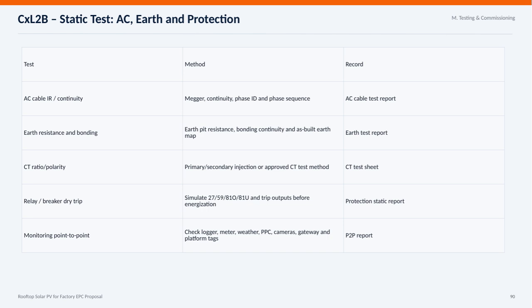Then we check the CT ratio and polarity through primary or secondary injection methods or other approved CT test procedures, recorded in the CT test sheet. For protection, we simulate various relay and breaker trips before energization, including functions like 27, 59, 81O, and 81U, ensuring protection systems operate correctly. These results go into the protection static report. Finally, we verify monitoring systems by checking loggers, meters, weather stations, PPC, cameras, gateways, and platform tags, with findings summarized in the point-to-point report. This comprehensive testing ensures all safety and performance measures are thoroughly validated before commissioning.